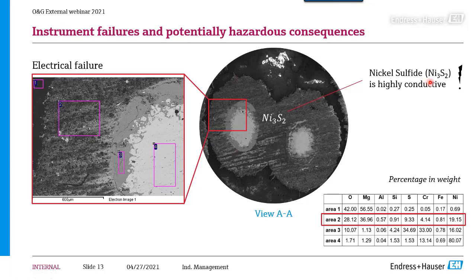What does that mean? It means we have Ni3S2, nickel sulfide. Thanks to the sulfur coming from the process, and the nickel that was part of the metal wires and outer sheath of the thermocouple, this nickel sulfide was created inside the thermocouple, and unfortunately it's highly conductive.